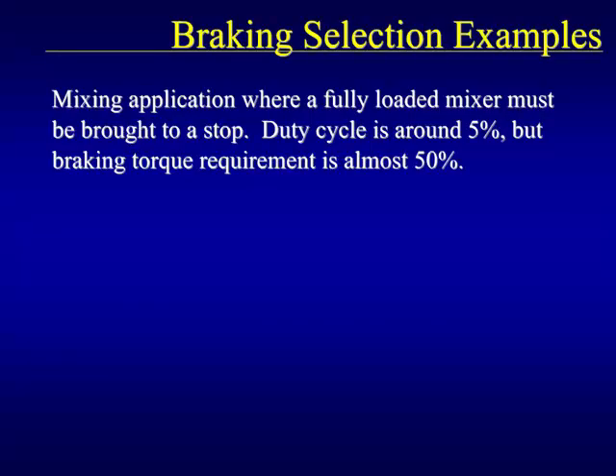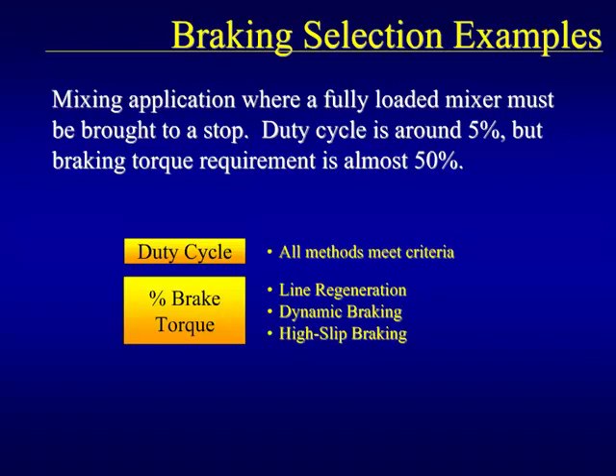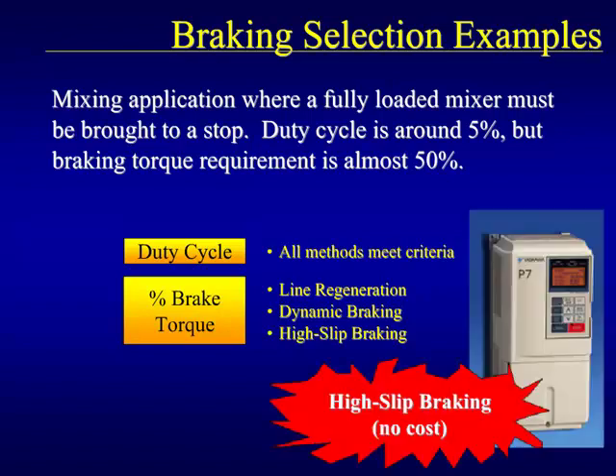Consider a mixing application where a fully loaded mixer must be brought to a stop. The duty cycle is around 5%, but the braking torque requirement is almost 50%. Comparing the application to the duty cycles provided for each braking method, all braking methods meet the duty cycle requirements. However, DC injection is not capable of meeting the braking torque requirements, leaving line regeneration, dynamic braking, and high-slip braking as the available methods. Because the application is a high-inertial load, high-slip braking would be the best method because it meets the requirements and requires no additional cost.